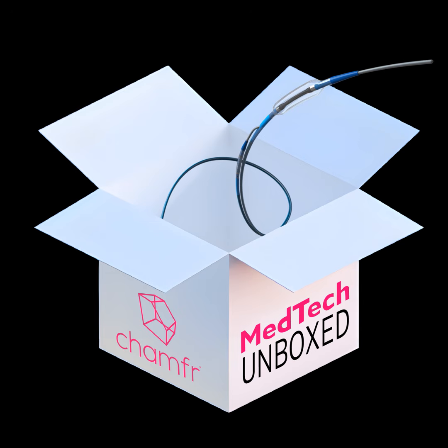And also, imagine back to our conversation earlier, in the very distal tip, how do I get it more flexible? If I'm still restricted by a high stiffness polymer like PTFE, then no matter how good a laser cut pattern I get at the distal, it's still going to be somewhat rigid, or you can force it, but you may brittle fracture that liner material. So in that kind of application, the lower durometer thermoplastic comes in handy. Number one, it will naturally bond to the stainless steel because it's nylon based, so you solve that reflow window problem. And not only that, because it's a lower durometer material, it will allow that distal section to flex better because it's more elastomeric, with a lower yield point, flexible. So that is a big discovery we have found: a lot of people want to utilize this material in a challenging design using laser cut.